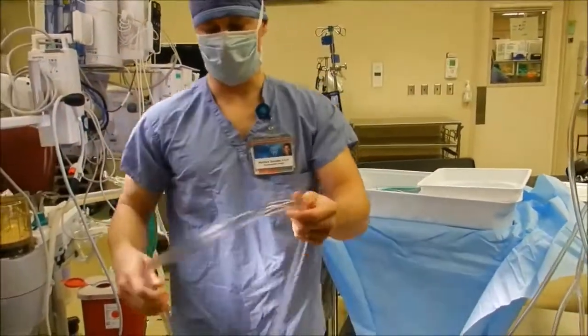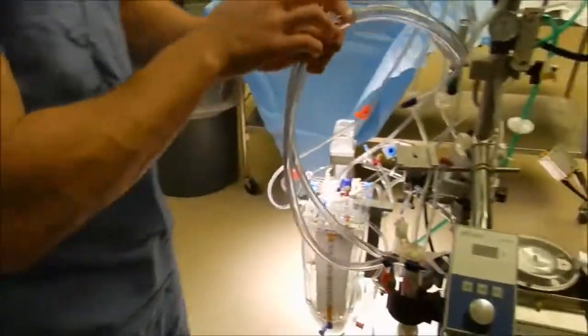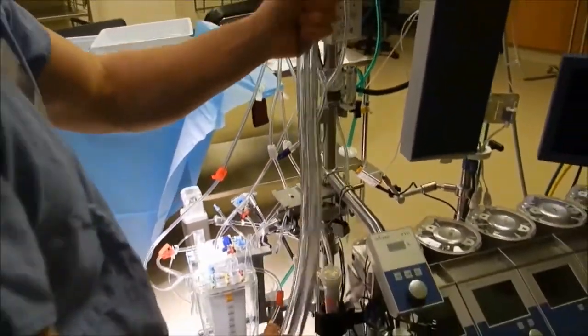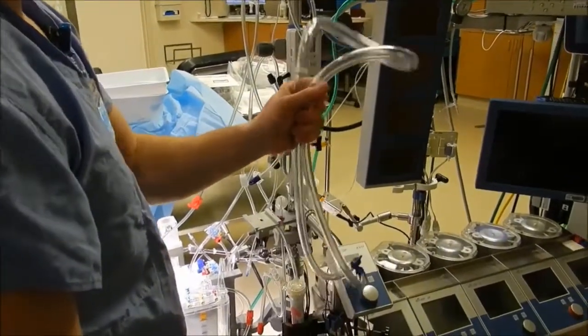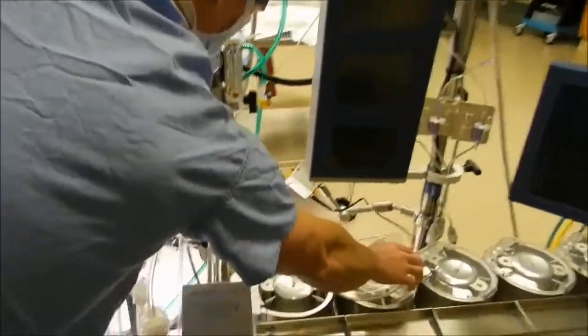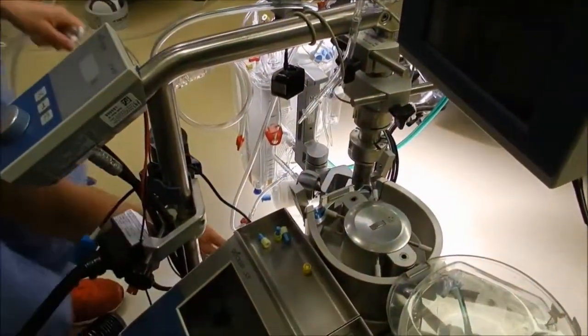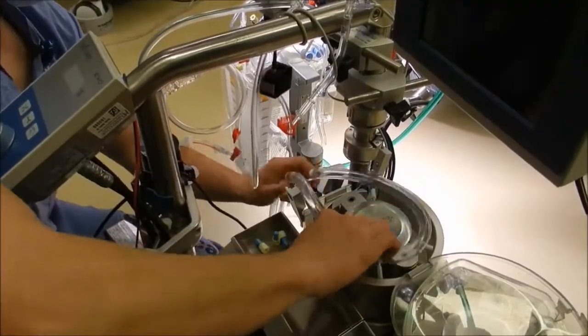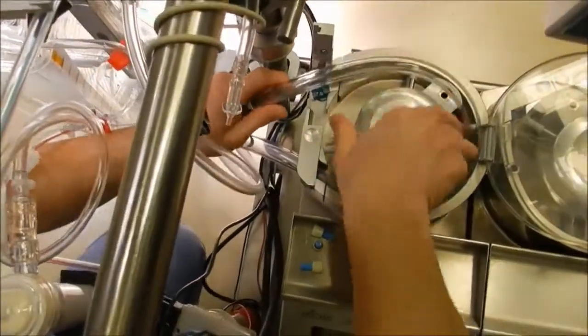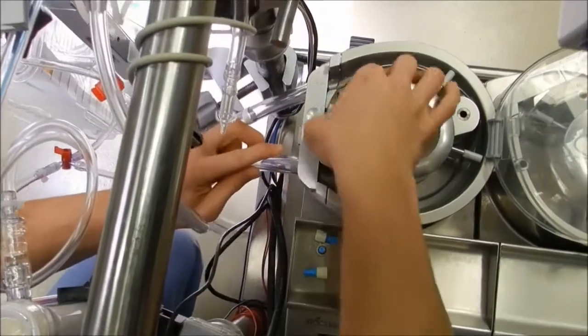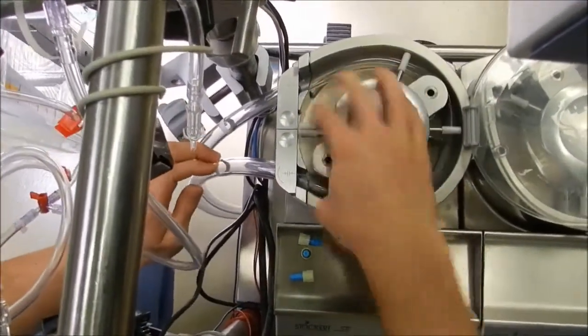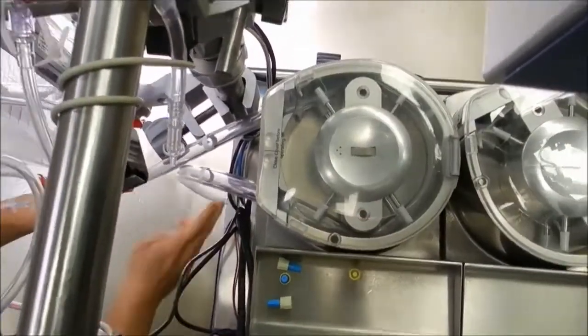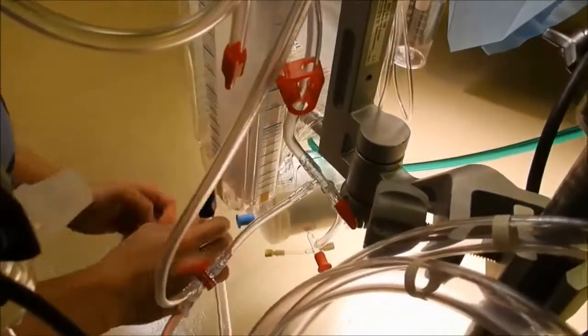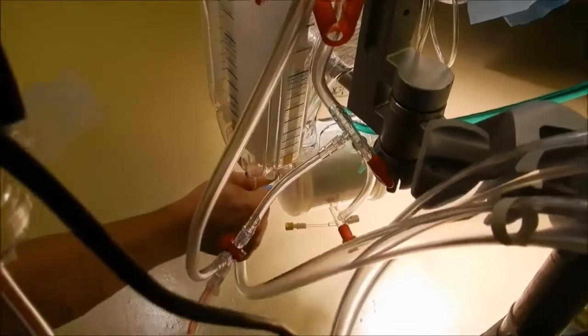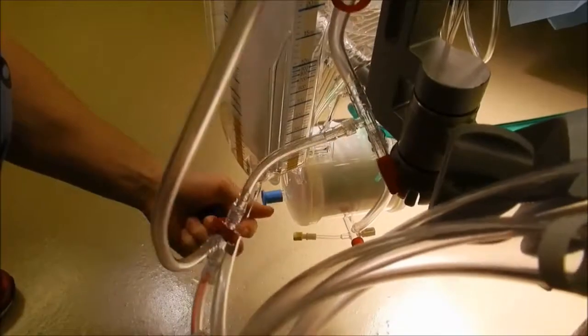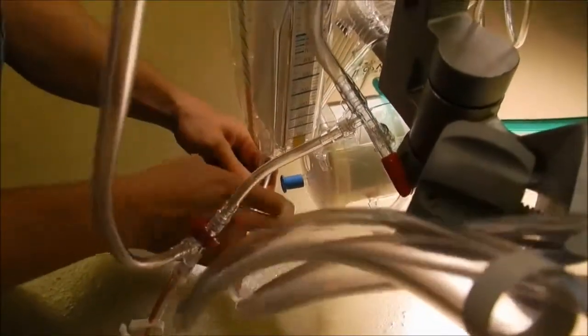We then have our boot for our arterial pump head. We have lines here. We have a tapered tubing, 3/8 to 1/2 inch. These lines tell you where the 1/2 inch tubing is, so you can place it correctly in your roller pump head. Get a good idea of the occlusion of your pump just by giving a turn. So inlet to the venous reservoir. Two barbs, please. And then we have the outlet of the arterial pump head, which goes into the inlet of the oxygenator.